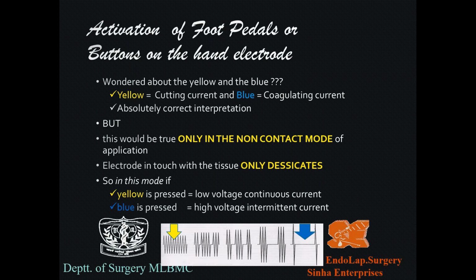Are you really doing that? You're not. Why? Because if your probe or the contact point is in contact with the body, you are not doing any cutting or coagulating. You are using the cutting and the coagulation mode. So yellow denotes cutting current, blue coagulating current. So what is basically the interpretation? The interpretation is that when you're depressing the yellow pedal, when your electrode is touching the body, then you're using a low current constantly, and when you're pressing blue, you're using high current intermittently.